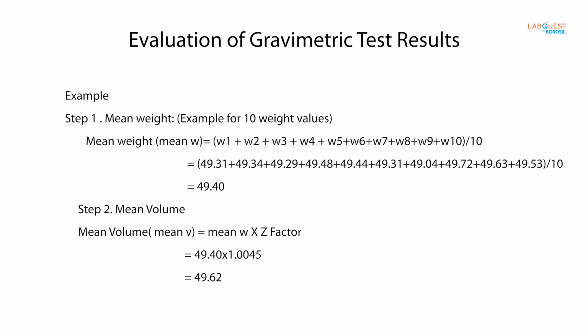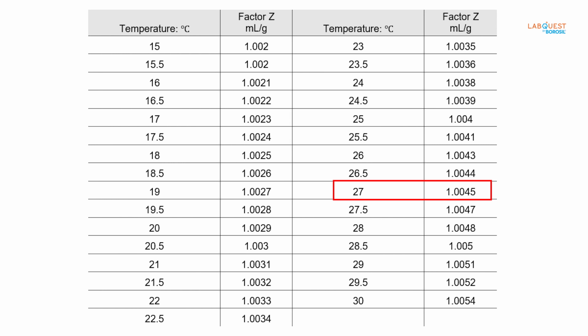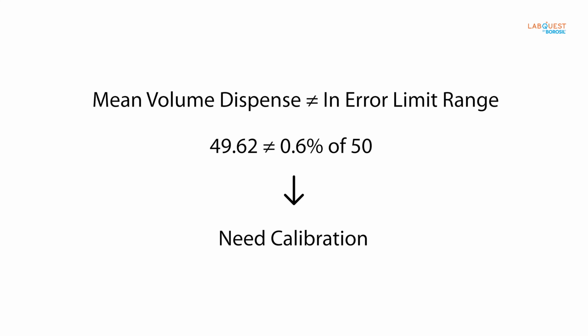Next, calculate the average weight from the 10 readings. To convert this mean weight into mean volume, you'll need to multiply it by a factor known as the Z factor. Refer to the provided table to find the appropriate Z factor. Then, use the provided formula to perform the calculation. Afterward, compare the gravimetric average result with the displayed volume. If there's a significant difference, it's time to recalibrate the dispenser.